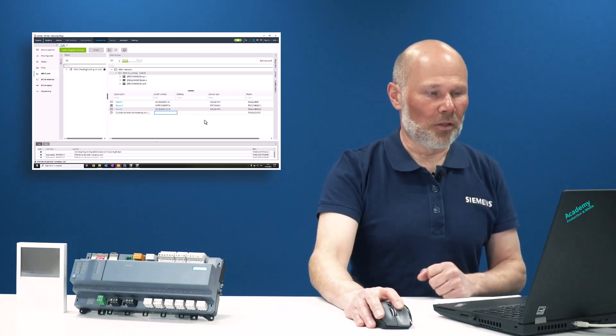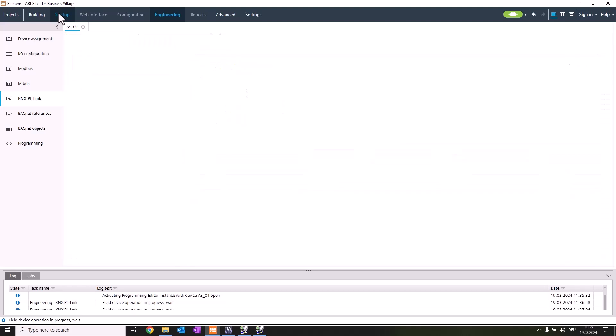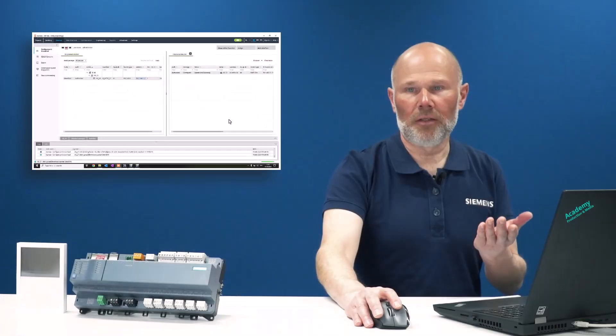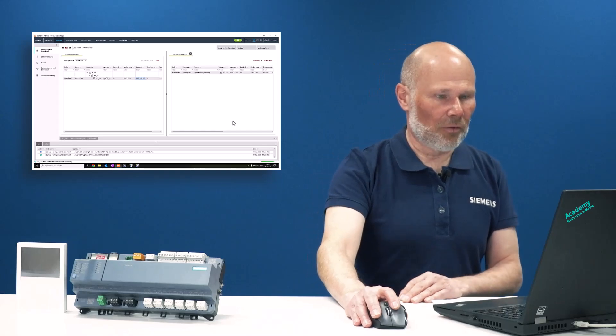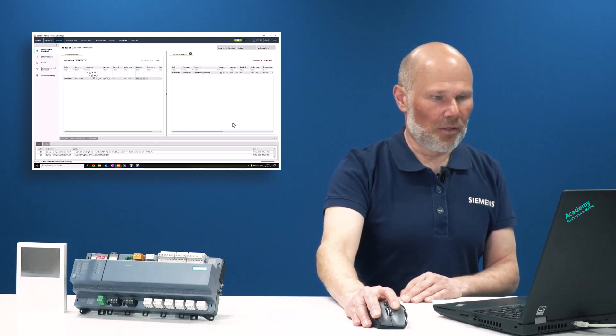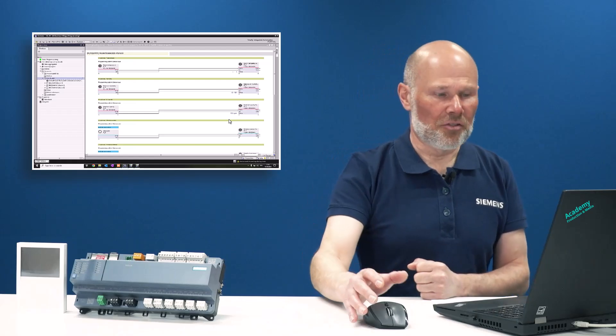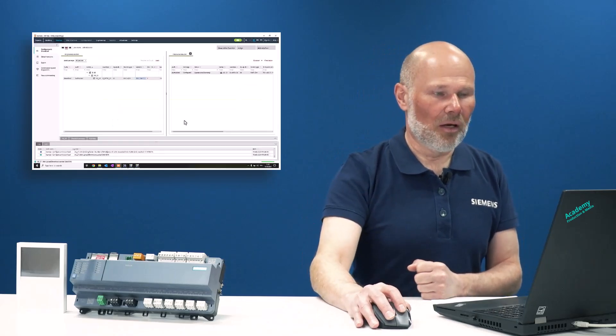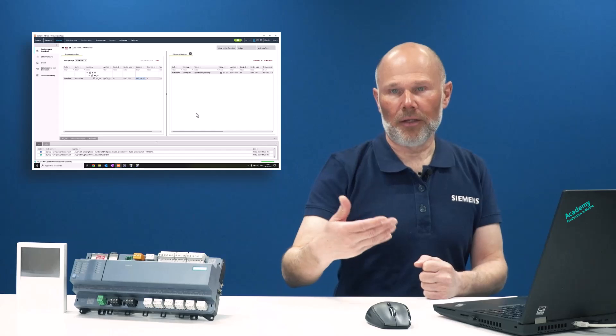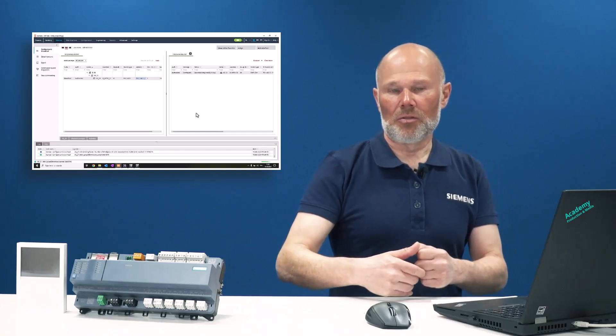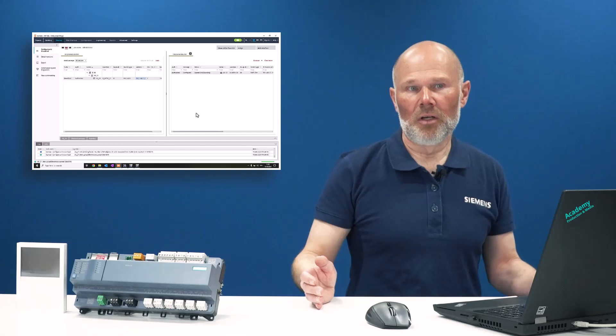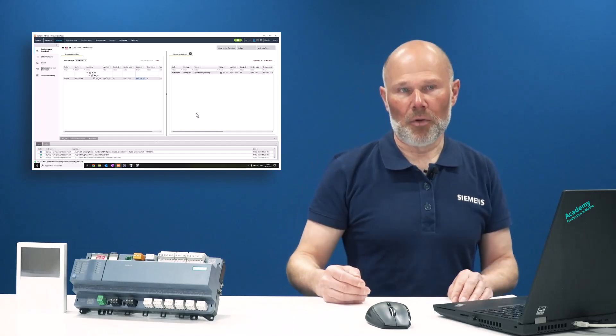Next step is startup. We re-download the changes into the automation station. It takes a moment, we're waiting for feedback from the automation station. As soon as it's downloaded, the pre-processing in the automation station will start and will automatically assign the RDGs. You don't have to do any single step more—the RDGs are already commissioned.